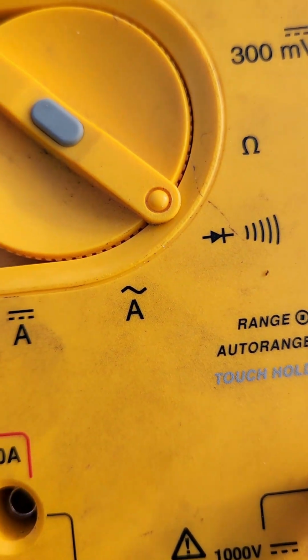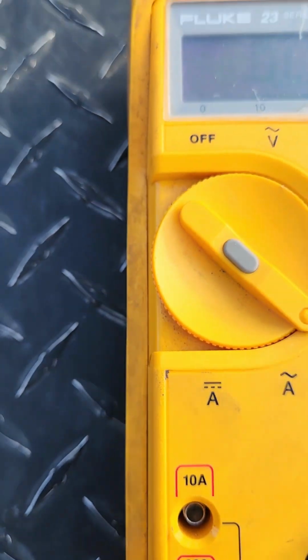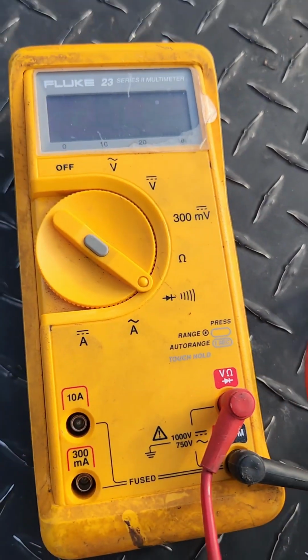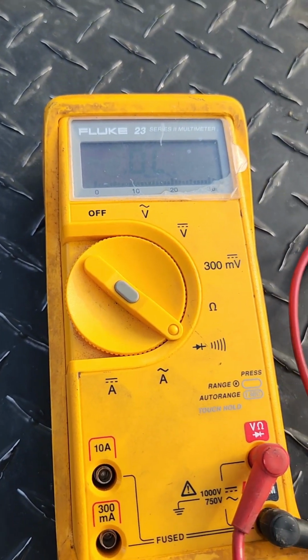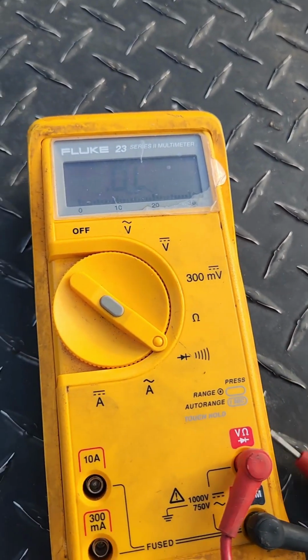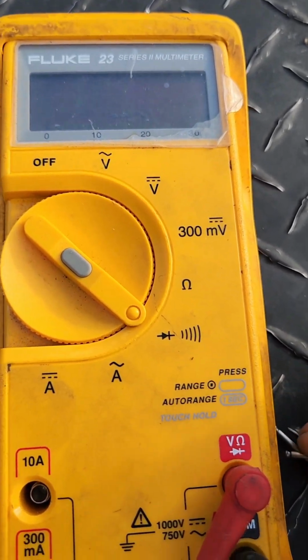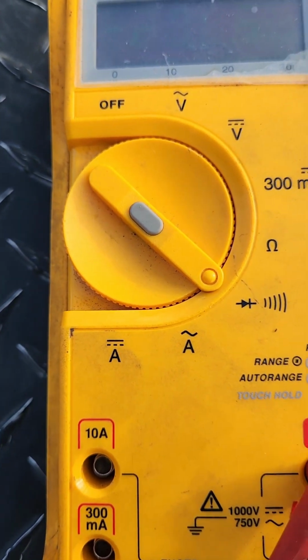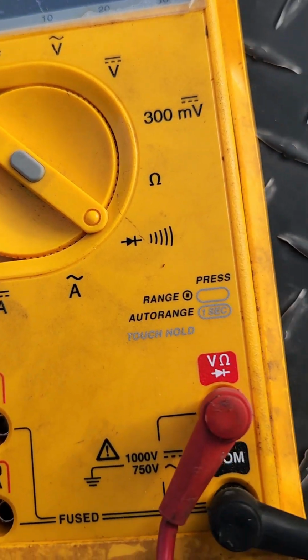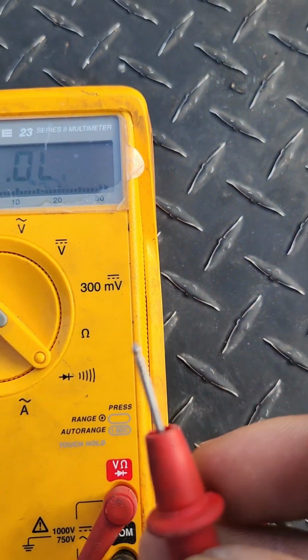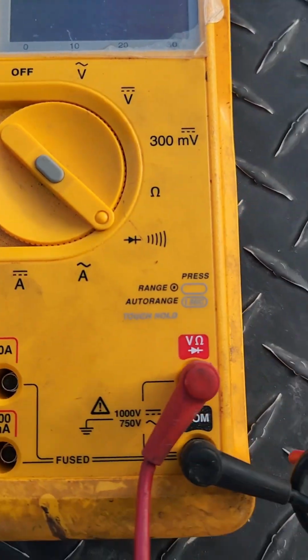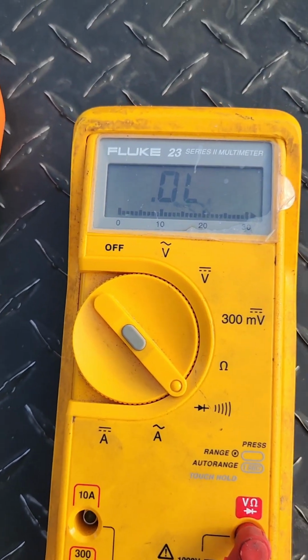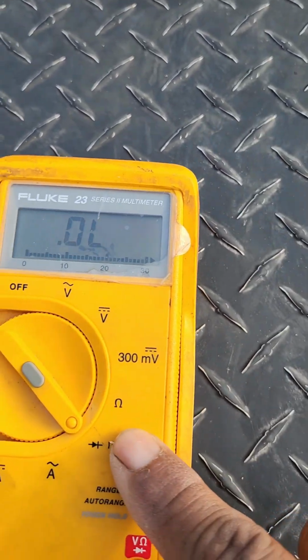It'll read 0 ohms if the fuse is good. And this one right here, you can check fuses and diodes. But the difference is, on this setting, you don't have to stand there and hold, you can just put it there and you can hear it. On this setting, it's basically the same as that one, but it just tests continuity. Hear the beep? The two lines are together. Checking the fuse, you can't really see the meter, you can just hear the buzz, and you know it's a complete circuit. So if you're checking a wire to make sure it's not cut, you put one lead on one end of the wire and one on the other end, and if it beeps, that means the wire is a complete circuit. So, in short, this one here is for continuity.